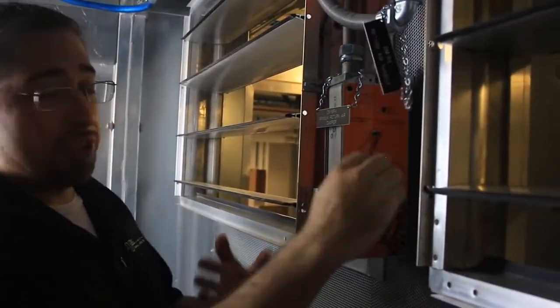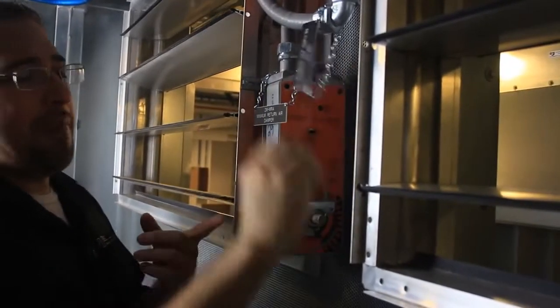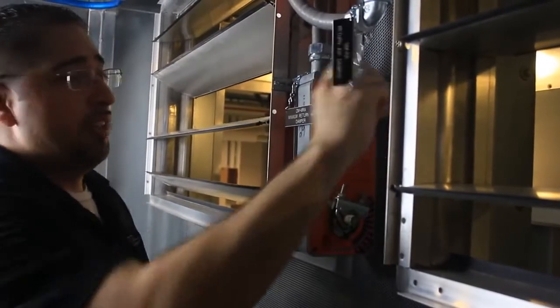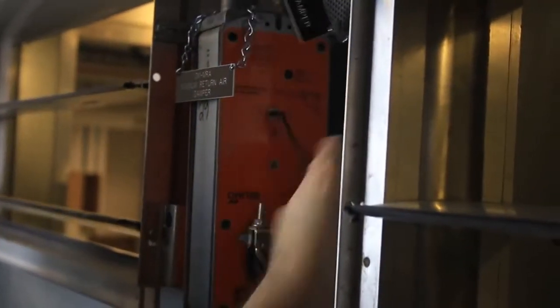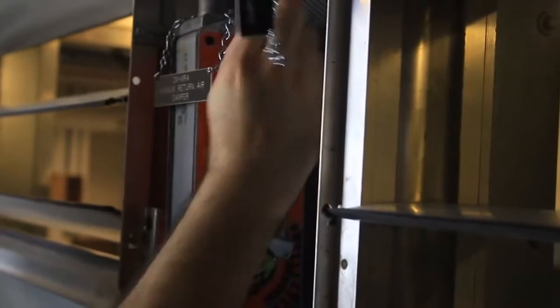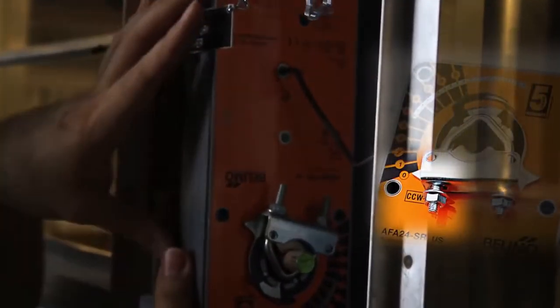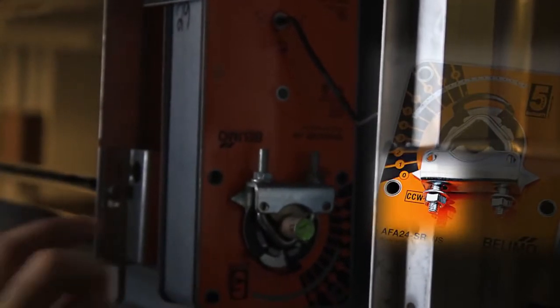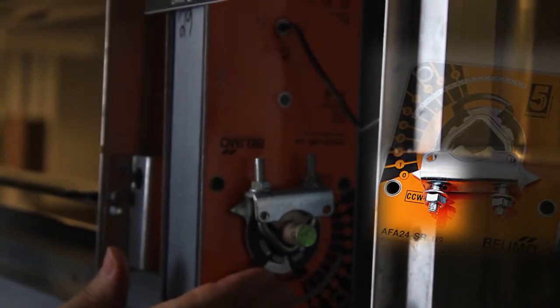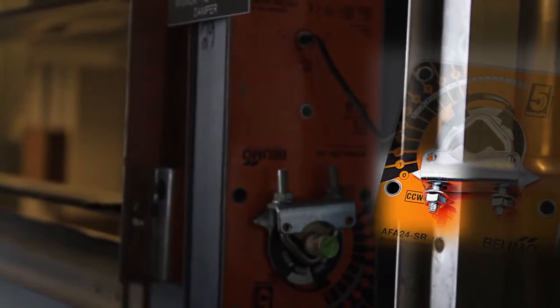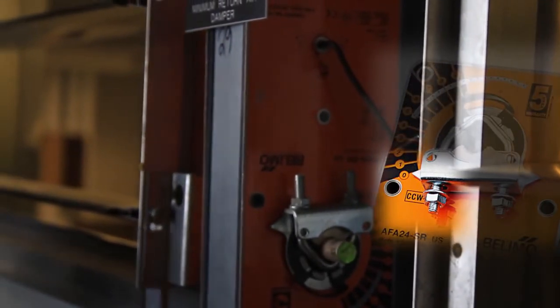Some other things with the spring return is, it depends on which way you mount this that you want the spring return. So in this case, I'm actually driving the shaft of this damper. And as you're looking at it, it's going clockwise. If you wanted to rotate the damper counterclockwise, all you have to do is mount this actuator, flip it around, and then stick it right back where it's mounted now. Then at that point, the spring return action would be spinning the shaft counterclockwise.